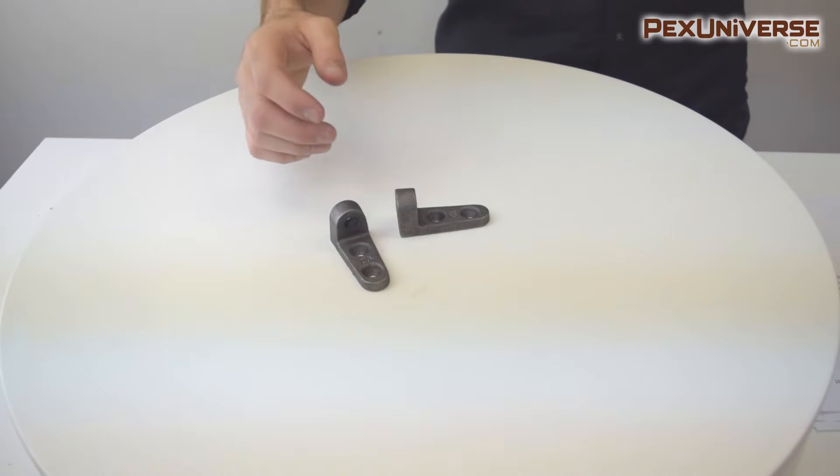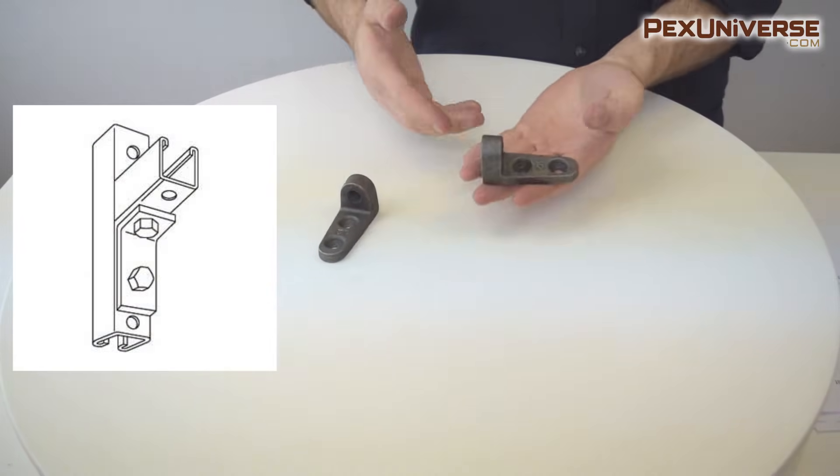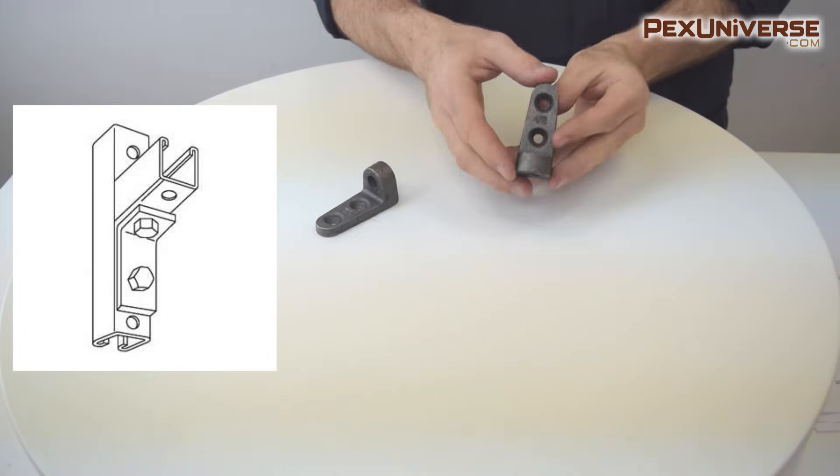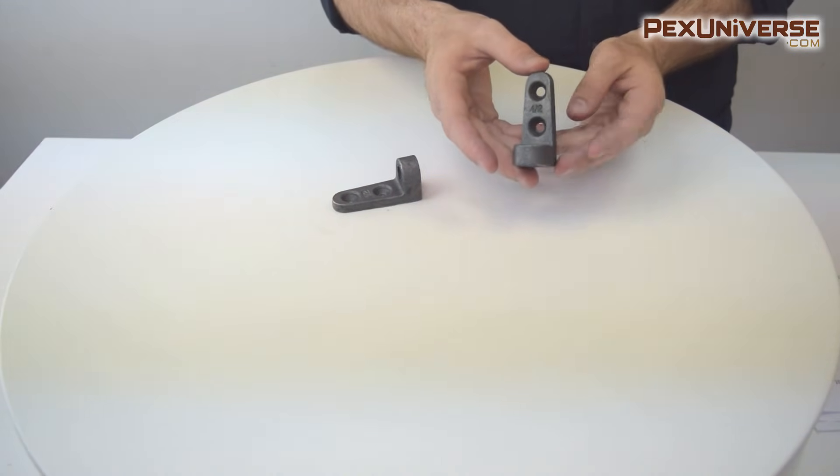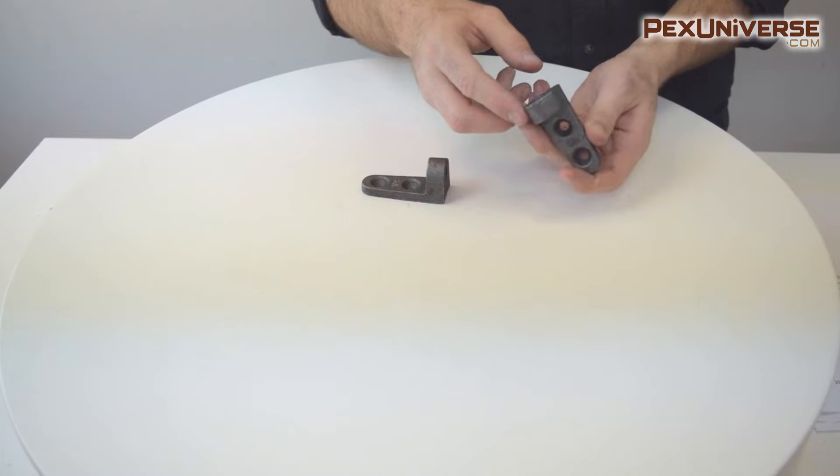Side beam connectors are designed for attaching rods to the side of wooden beams or walls. It secures a standard threaded rod, either 1/2 inch or 3/8 of an inch, to the side of a wooden or metal beam.